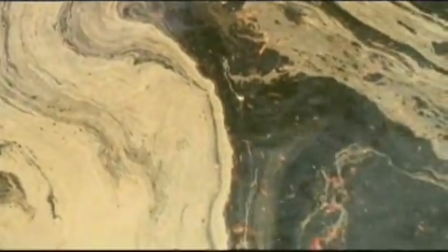For the purpose of this program, conventional coagulation, flocculation, sedimentation, and filtration processes are illustrated for the removal of particulate matter from turbid waters. The particles that cause turbidity consist mostly of non-settlable solids. These particles typically do not settle out of water because of two factors: particle size and the natural repelling forces between particles.